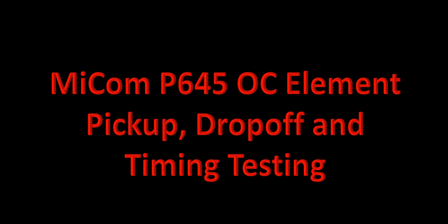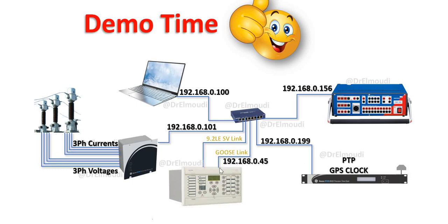Let me show you the concept diagram where we're going to see clearly what we're going to do. So here, the test set is going to inject a current through sampled values to the MiCOM relay. And we're going to start increasing that injected current until it reaches the pickup of the relay. When the relay overcurrent element starts picking up, we're going to capture that as a GOOSE message. So we need a GOOSE message that represents the start of the overcurrent element.